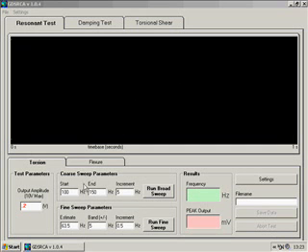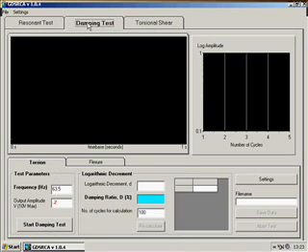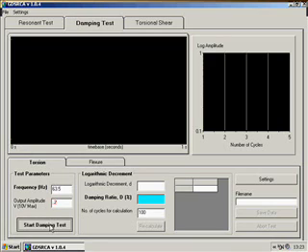Now we have found the resonant frequency of the sample of 63.5 hertz. We can go on and perform a damping test. We run this test at the resonant frequency, 63.5 hertz, and again I am going to choose an example amplitude.